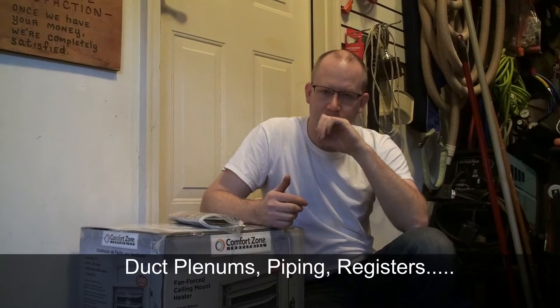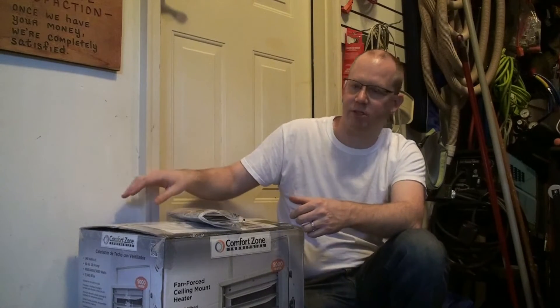I thought if I went with a PVC-vented 92% furnace I could just vent it out the side myself and the fittings would be negligible. But even then it was still about $500 to $700 for the fittings needed to put it in the garage. There's also a clearance issue — the unit has to be 18 inches off the ground and I'd be really close to that. The solution would've been to go up the wall slightly and vent it out through a stud bay, but that's not ideal. So forced hot air — whether 80% or 92% — wasn't really happening.